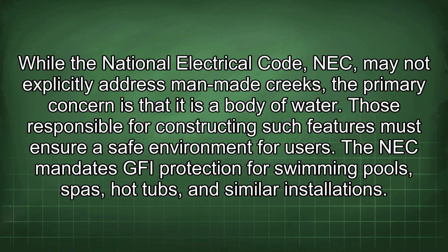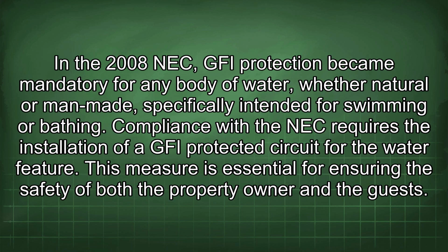The NEC mandates GFI protection for swimming pools, spas, hot tubs, and similar installations. In the 2008 NEC, GFI protection became mandatory for any body of water, whether natural or man-made, specifically intended for swimming or bathing. Compliance with the NEC requires the installation of a GFI protected circuit for the water feature. This measure is essential for ensuring the safety of both the property owner and the guests.